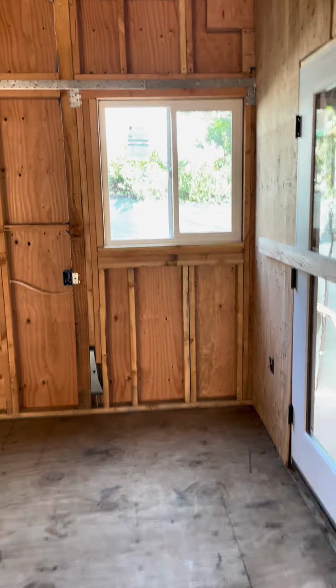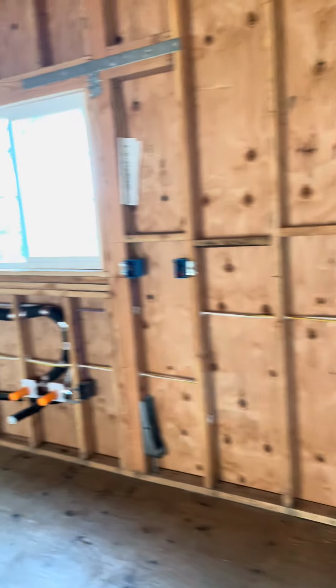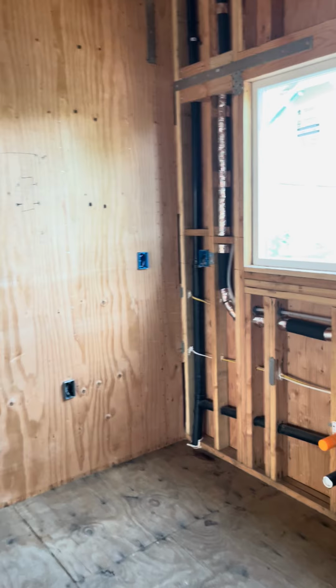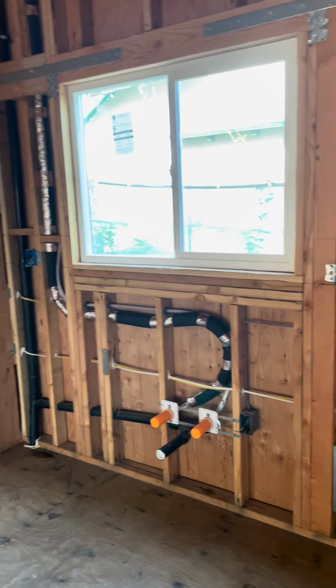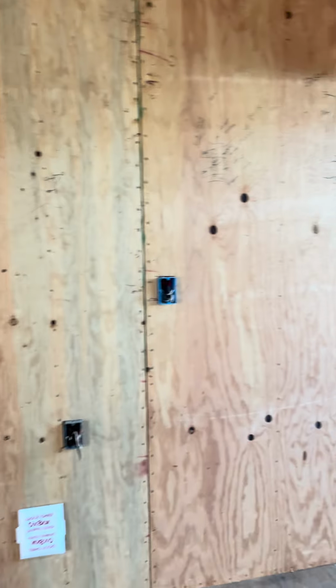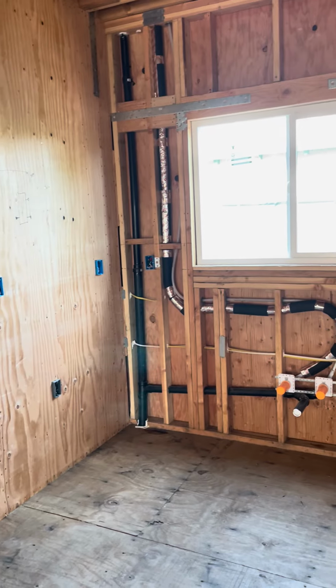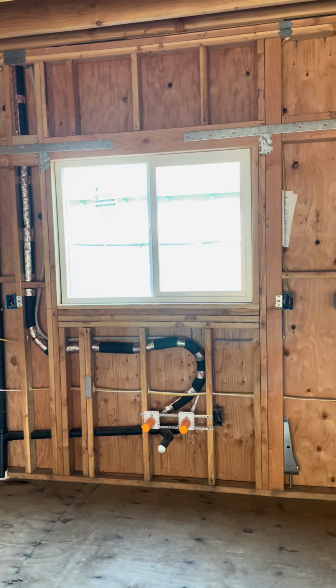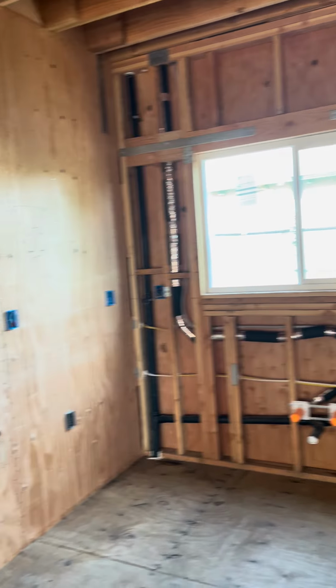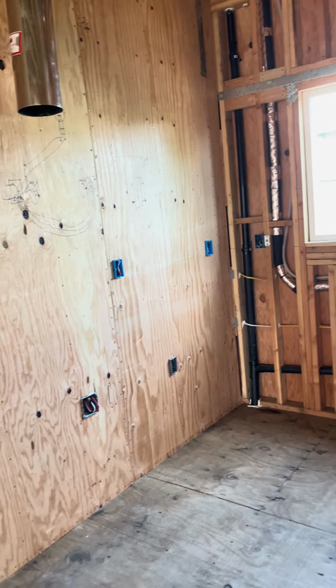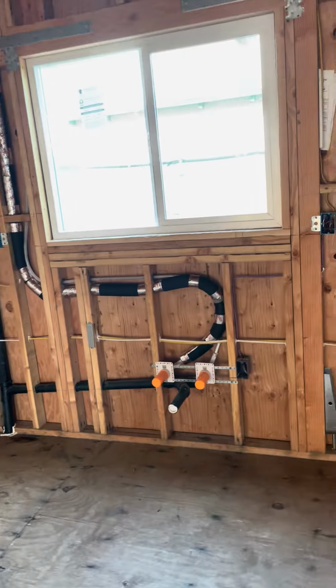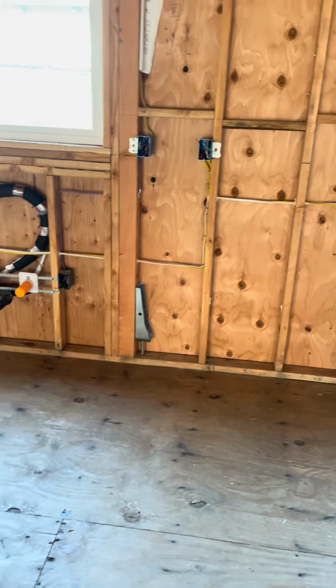And here we are looking at the kitchen. We have 2 dedicated appliance circuits. That is a code requirement, so that should be something all electricians listening to this should know and remember. And if you don't know, now you know. 2 appliance circuits. Garbage disposal has to be on its own circuit. We have an outlet here for the plug, and it's on the same circuit as the appliance circuit.